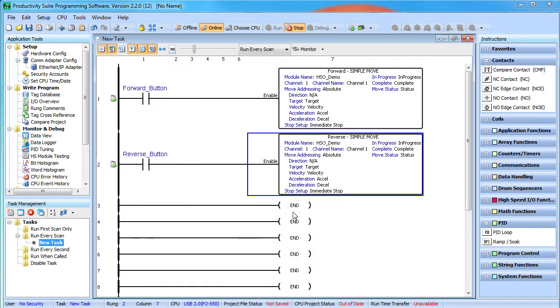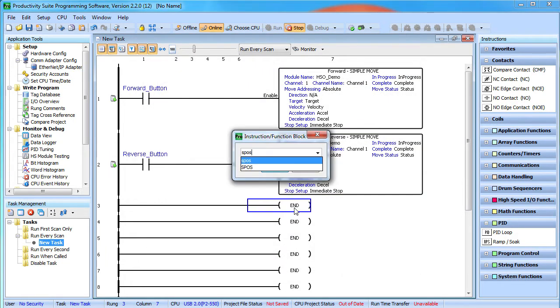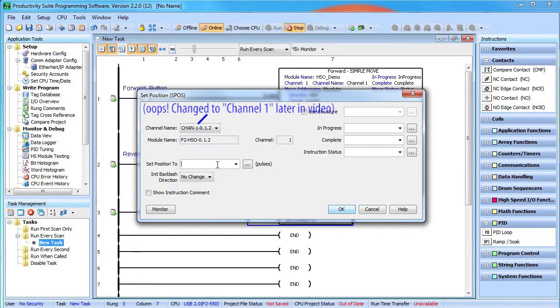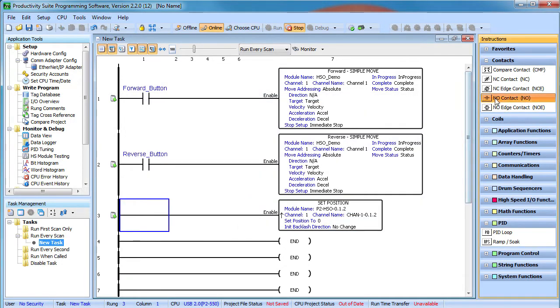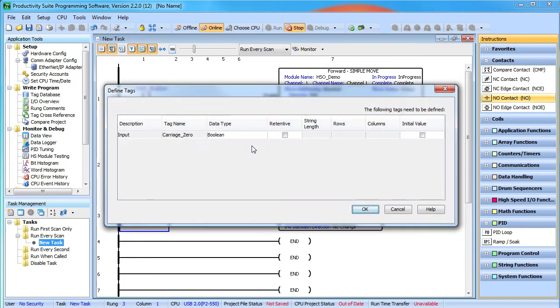We also want to be able to force the HSO module's channel position to zero. Since the module keeps track of the position from the time it is turned on, the only way to reset the position is with the SET POSITION command. We just tell it to set the position to zero when this instruction is enabled. And we'll enable it with a contact that we'll control from the data view since I don't have any more buttons connected. Let's download this to the processor and give it a try.